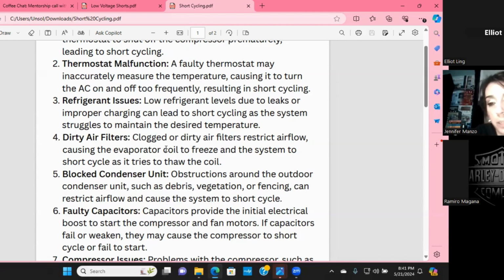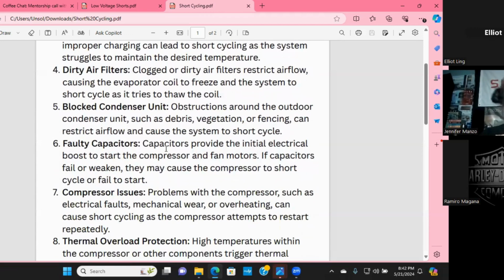Dirty filters need to be changed as often as humanly possible. Dirty condenser coils need to be washed as often as humanly possible. And dirty evaporator coils absolutely need to be watched and taken care of because evaporator coils, what happens is the nastiness on it tends to then get condensation within it. And it turns to a concrete-like substance that is very hard to get off. And that will stop your AC right in its tracks.